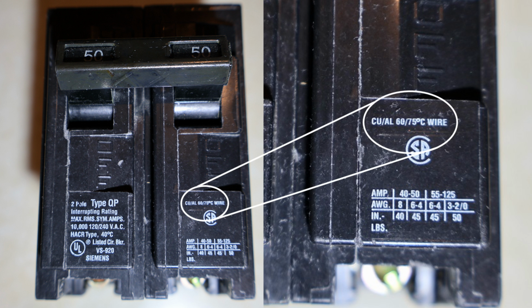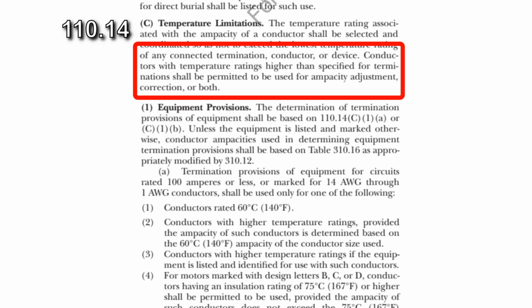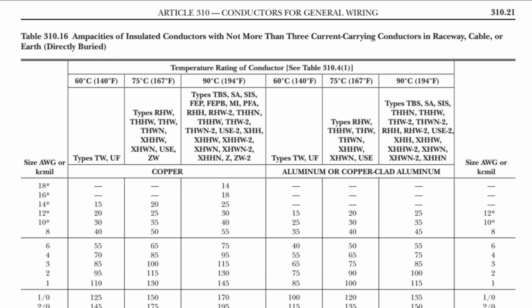Most circuit breakers have 75 degree terminations. The terminations on this Siemens circuit breaker are labeled in tiny fine print, but with a magnifying glass we see the terminations are rated for use with aluminum or copper conductors with ampacities in their 60 degree or 75 degree column. You can use 90 degree rated conductors here, but only at their 60 degree or 75 degree ampacities. Next part. Conductors with temperature ratings higher than specified for terminations shall be permitted to be used for ampacity adjustment, correction, or both. So when we're doing ampacity corrections on these conductors, we can apply our derating factors to its higher temperature rating to derive its derated ampacity value. But we still can't exceed the temperature rating of the termination. Keep that in mind.